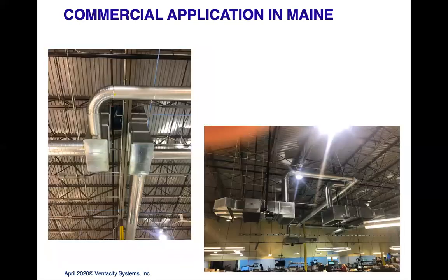On the left, underneath the ERV, is the supply and return distribution inside a commercial facility. This is a digital print facility. What we did with the fresh air ventilation is duct it to the air handlers for the VRF heat pump system and then distribute it through their return plenum. In some cases, if we need to do a little bit of extra tempering of that air, we can do that. In this case, we're mostly looking at dehumidification in the summer, so we can run it through the heat pump and do some additional dehumidification.